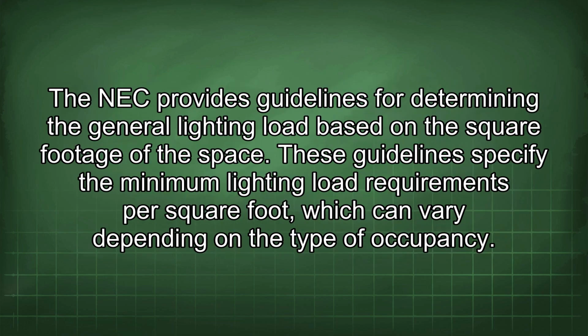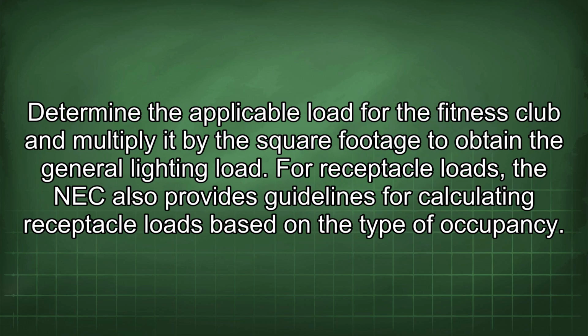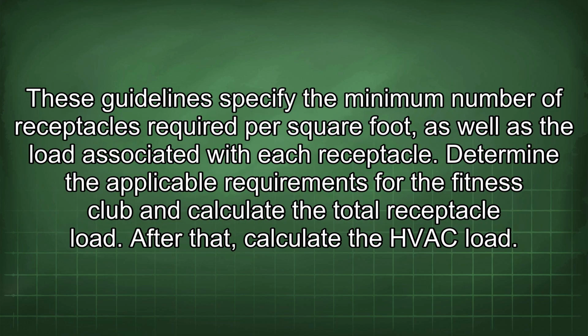Next, calculate the general lighting load. The NEC provides guidelines for determining the general lighting load based on the square footage of the space. These guidelines specify the minimum lighting load requirements per square foot, which can vary depending on the type of occupancy. Determine the applicable load for the fitness club and multiply it by the square footage to obtain the general lighting load. For receptacle loads, the NEC also provides guidelines for calculating receptacle loads based on the type of occupancy. These guidelines specify the minimum number of receptacles required per square foot, as well as the load associated with each receptacle. Determine the applicable requirements for the fitness club and calculate the total receptacle load.